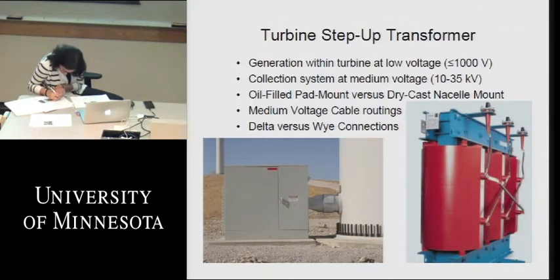In a small distribution transformer, you generally don't have forced air and pumped oil cooling, so you're relying on the natural ambient air moving over cooling coils to cool off the tank with the oil in it in the transformer. So when the wind picks up and provides more power, which would heat up the transformer, it also tends to provide more cooling for the transformer.